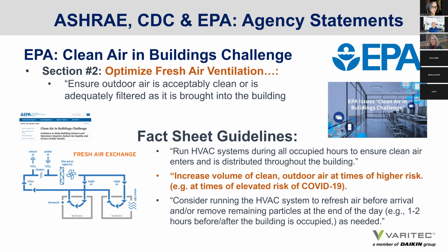The EPA also goes on to state, in their Clean Air in Buildings Challenge initiative, the aim to optimize fresh air ventilation, to improve indoor air quality, and to reduce the concentration of contaminants in the air. And one of the ways to do that is to increase the volume of clean outdoor air at times of higher risk, especially during a pandemic. And there's a whole other issue developing here with ASHRAE's recent Standard 241 that considers outside air as one of the adequate ways of providing clean air to the breathing zone during pandemic mode. But anyway, there are some developments on that end with ASHRAE in looking at outside air. So stay tuned for that.